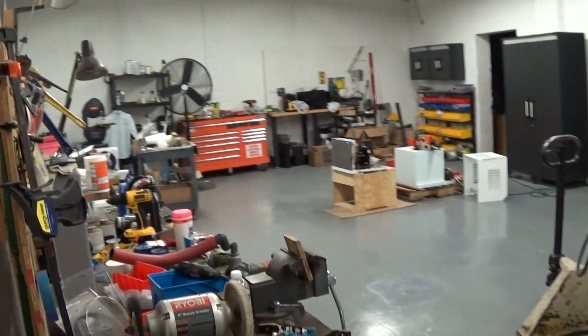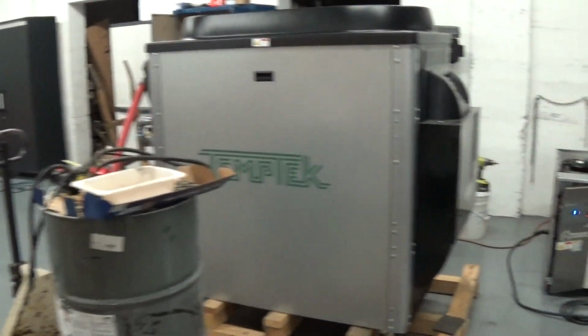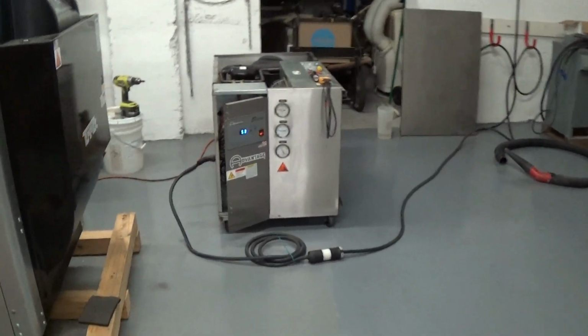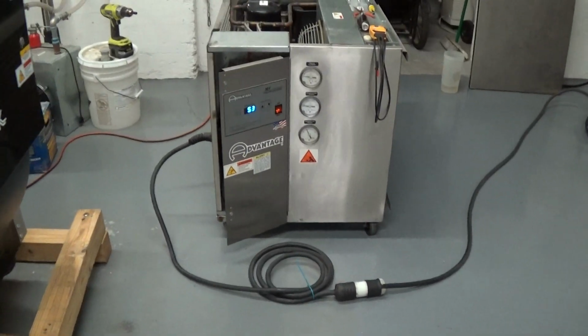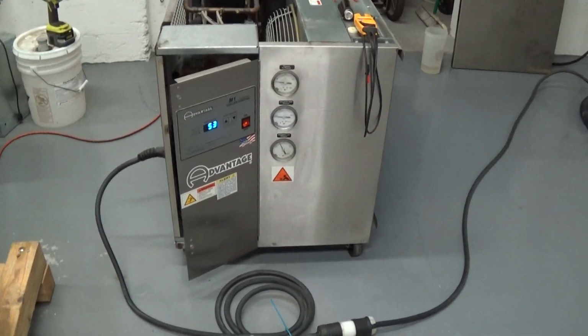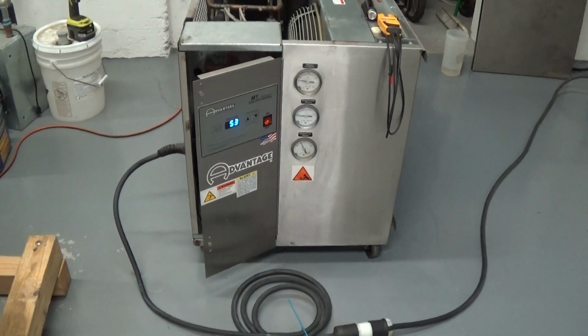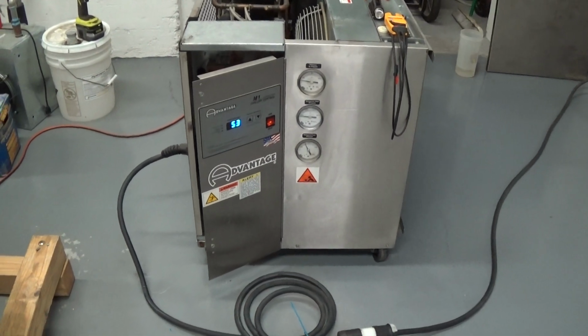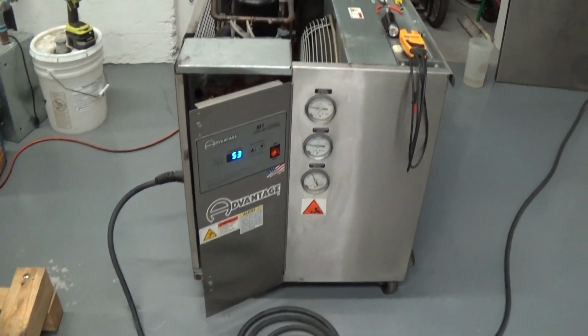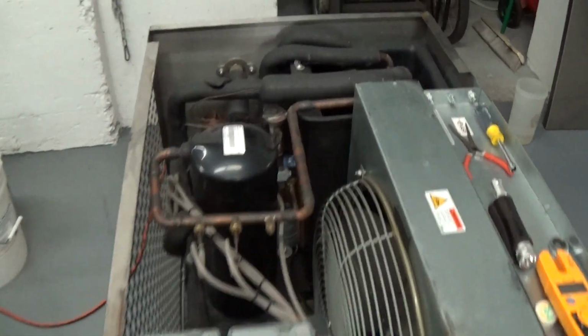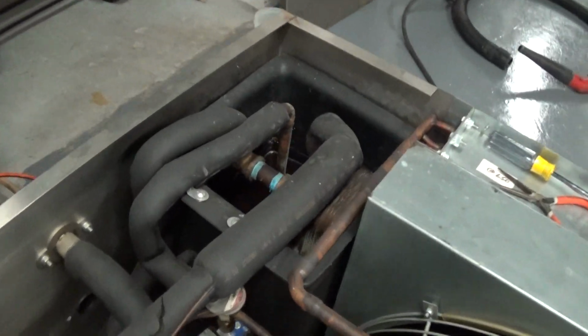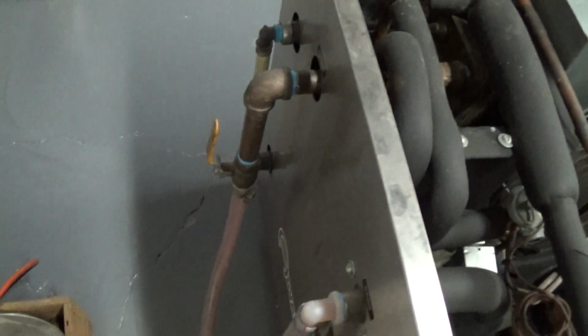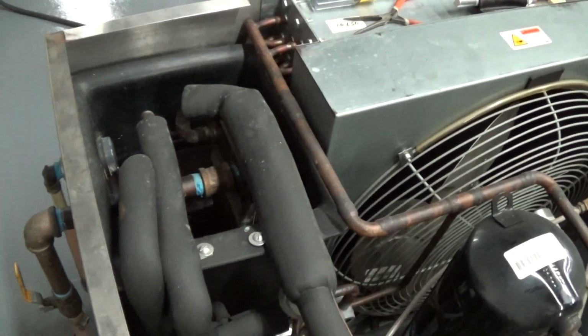We're in our small chiller test area here in Clinton, Massachusetts, and we're going to do a quick little pull down test on this Sold Advantage/Temptek 2-ton air-cooled chiller. We have a little bit of glycol and set up a glycol loop, and we've tested this before here in the reservoir tank.